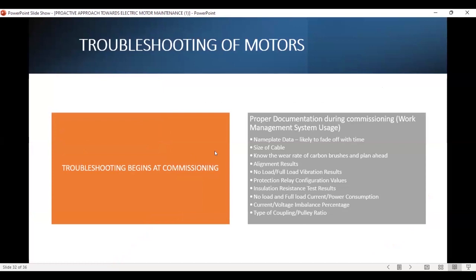In terms of commissioning, proper documentation is very, very important. As you install a motor, the nameplate data is likely to fade. So you get your proper documentation and you put the motor nameplate data on your work management system, so that in case of future analysis, you know the nameplate data and you know what to do. The size of cable which was used must be documented and put in your work management system.